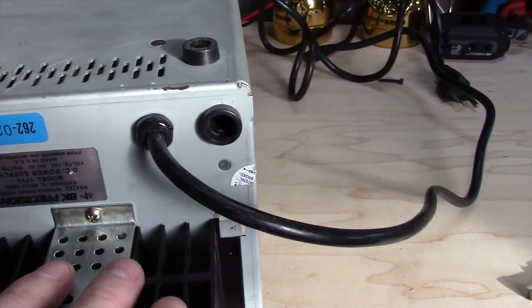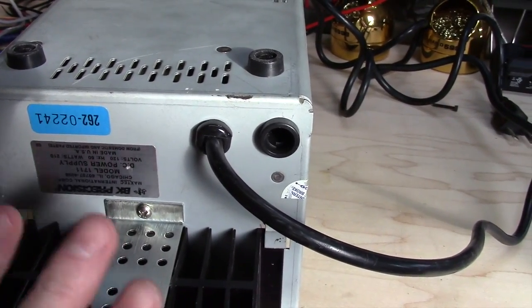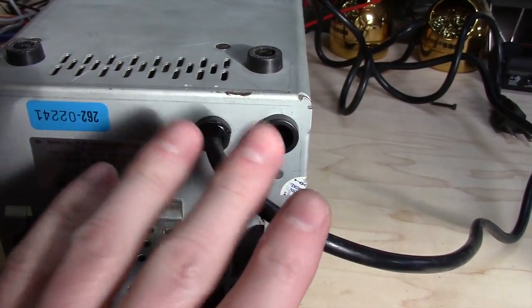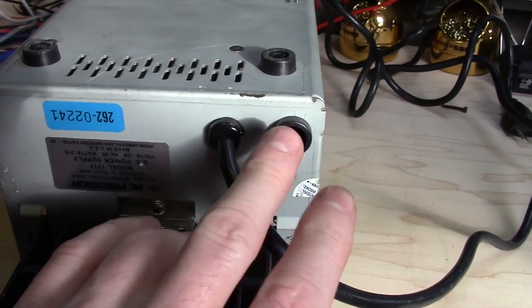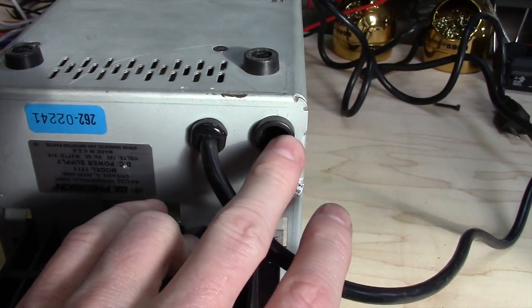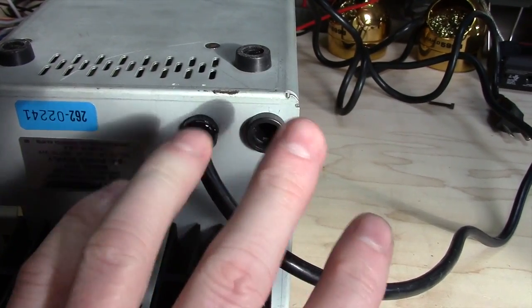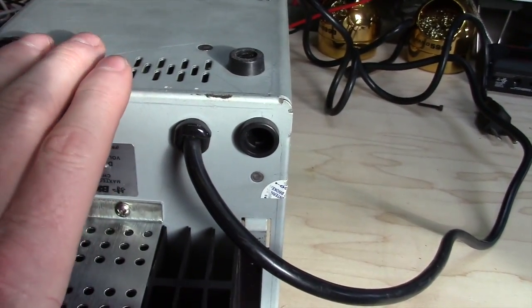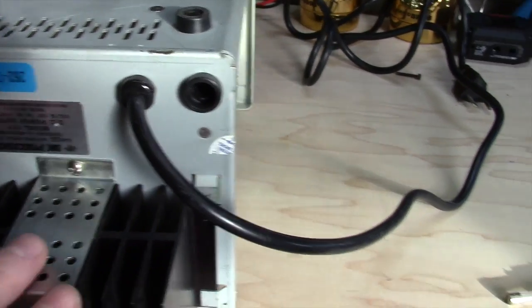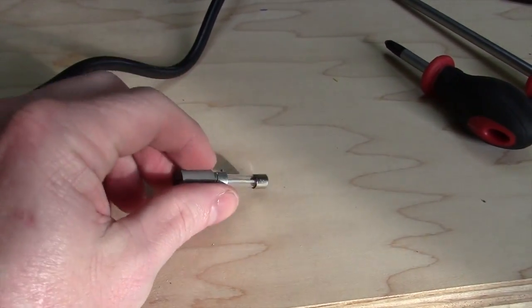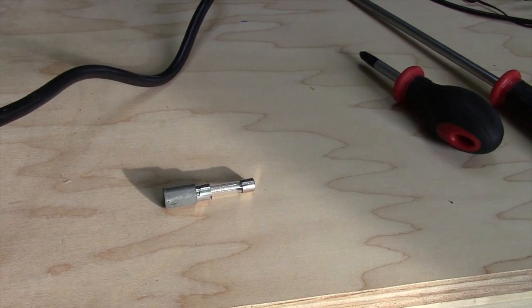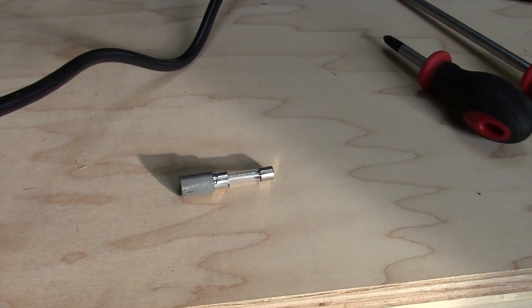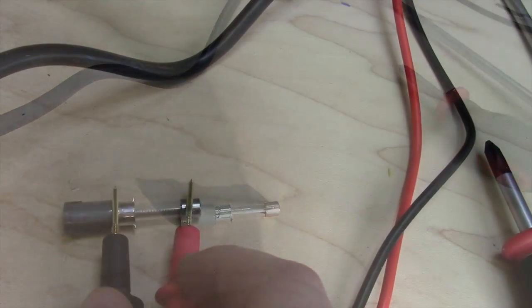Generally one of the first areas you want to check on any device. I don't really recommend, if you find a bad fuse, there's something wrong. Something else has happened, and if you do find something like that, you need to really look ahead of what may have caused it to happen. On this particular unit, the fuse looks perfectly fine. We'll check it here with an ohmmeter just to verify, but that doesn't appear to be what the problem is.